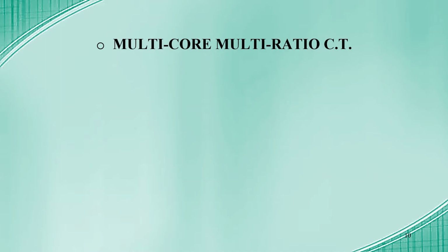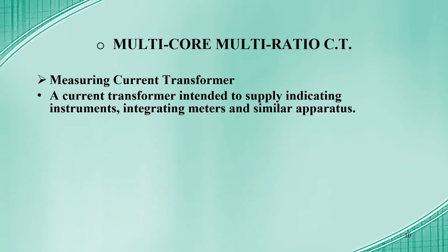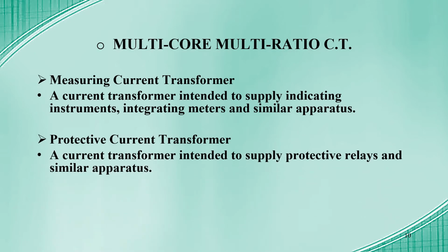And multiple core CTs are provided with multiple ratios so that in case in future the demand increases, the same CT can be used for a higher capacity, thus making it cost effective. Its functions are as below: measuring current transformer and protective current transformer. Both these functions are provided by multi-core and multi-ratio CT.